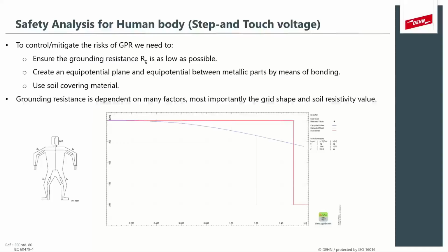So the fault current is going to be the fault current from the electrical system, but we can adjust the grounding resistance as much as possible to ensure a low voltage or ground potential rise at ground surface level. We can also create an equipotential plane between metallic parts by means of bonding, meaning that we will ensure the voltage is the same across the area where people can walk, so that there are no differences for step potential, and also no differences when touching metallic parts with reference to the voltage experienced at ground level. Then one of the other methods is to use soil covering material. That's typical where you would see washed granite or substation gravel that covers the surface layer of the entire substation.